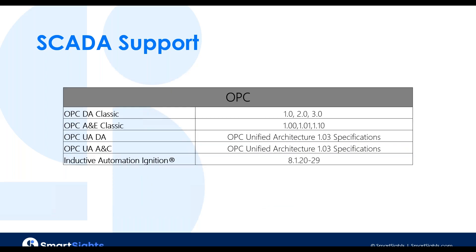We do have an expanded OPC portfolio. We can connect to OPC DA and OPC UA DA, OPC A&E and OPC UA A&C. If you're an Ignition user and want to connect to WIN-911, we have built an OPC UA server for it — you embed it into your Ignition application, then use our OPC UA Alarm and Conditions client to connect, pulling alarms in as if it were a native SCADA connection. That's pretty exciting.